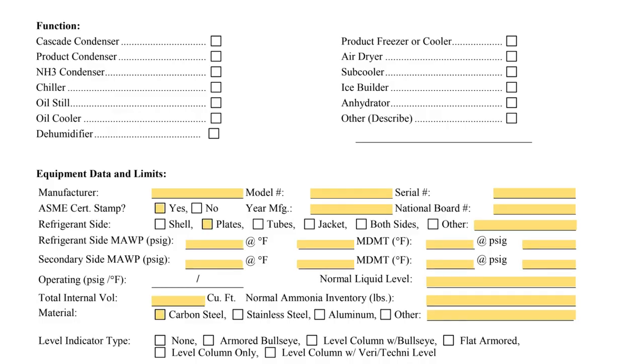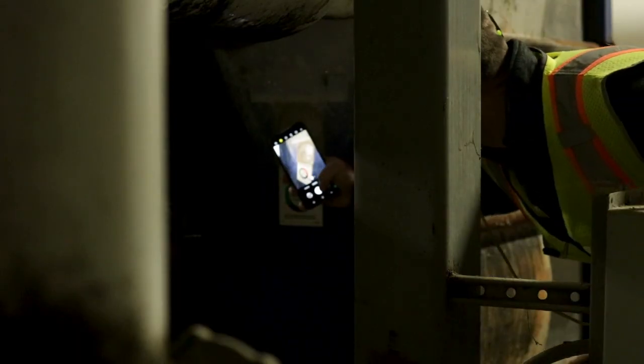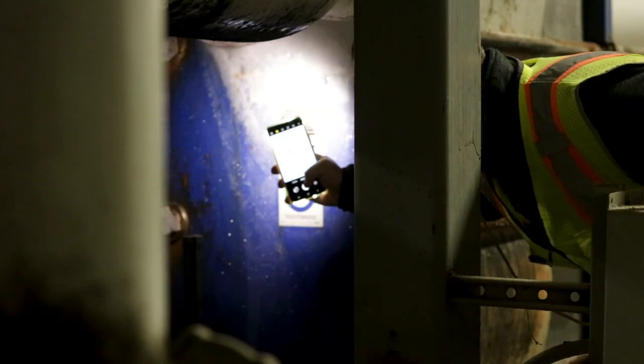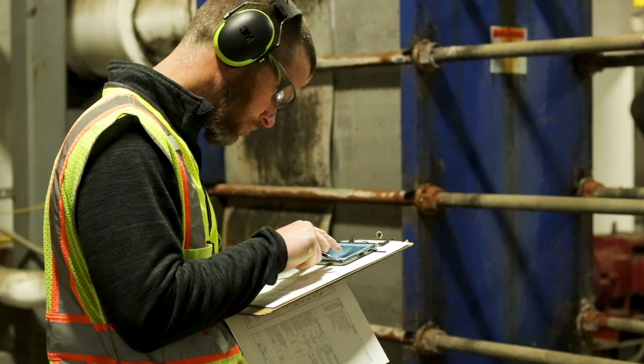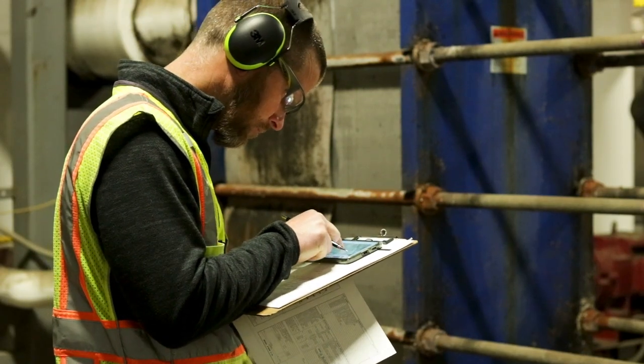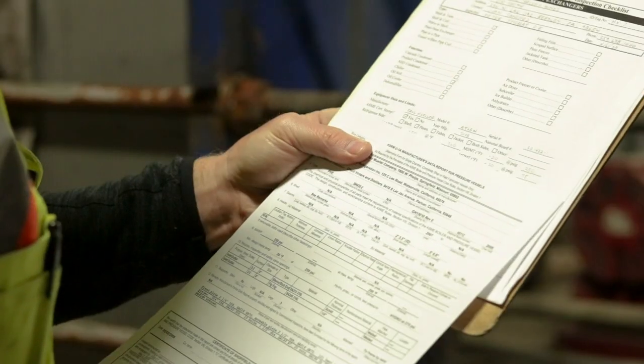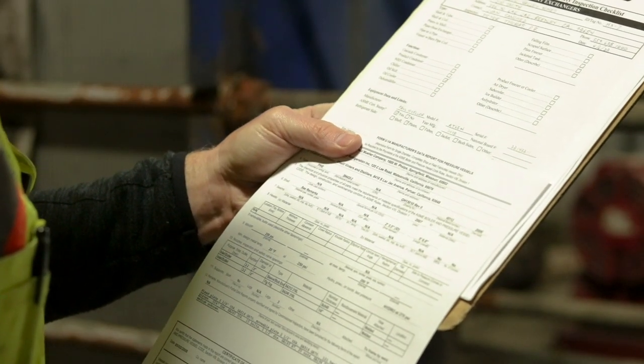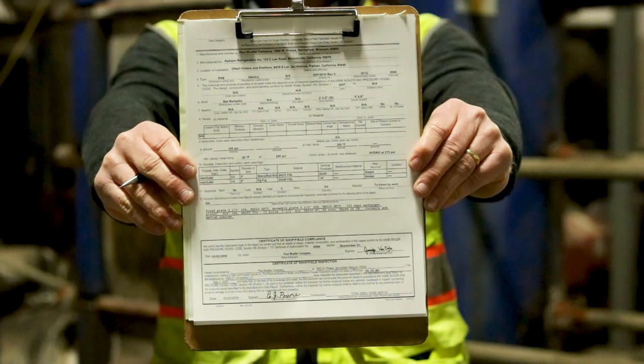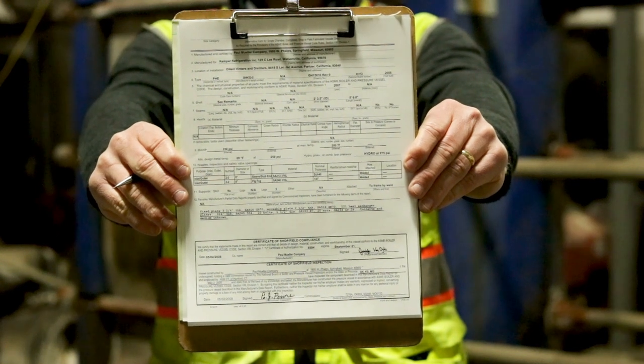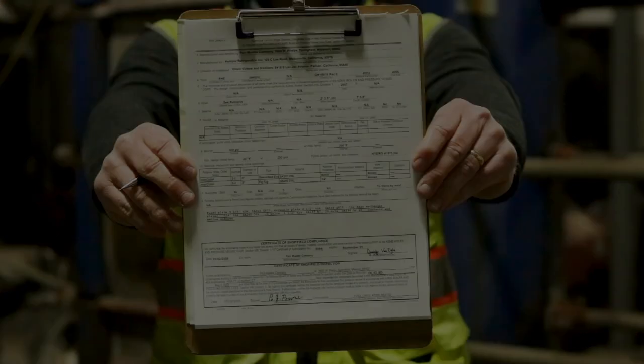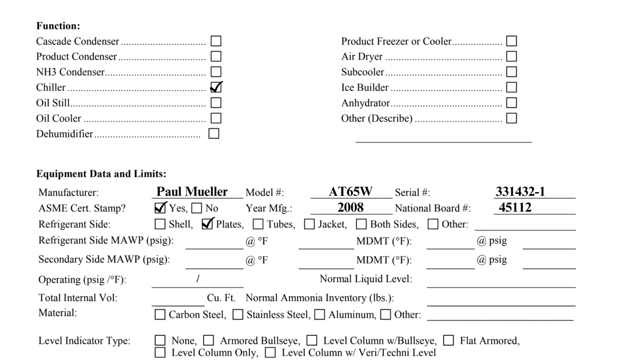Much of the information requested in the section titled Equipment Data and Limits can be obtained from the heat exchanger nameplate. A camera can be useful for difficult-to-reach nameplates. The nameplate for this plate and frame heat exchanger is only partially legible, so the Manufacturer Data Report, or U1A form, can be referenced to fill out the information that cannot be deciphered on the nameplate.